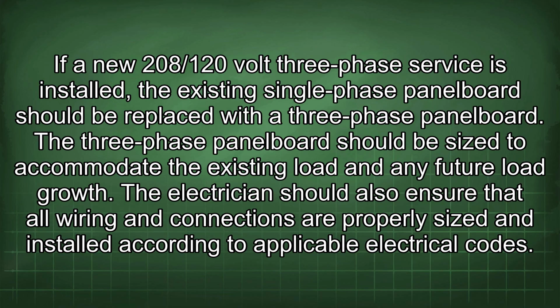If a new 208/120 volt 3-phase service is installed, the existing single-phase panel board should be replaced with a 3-phase panel board. The 3-phase panel board should be sized to accommodate the existing load and any future load growth. The electrician should also ensure that all wiring and connections are properly sized and installed according to applicable electrical codes.